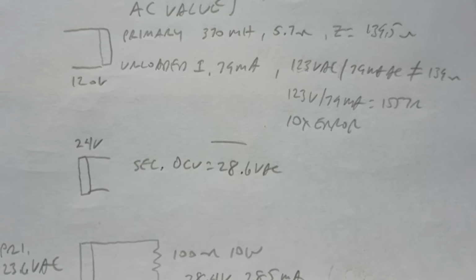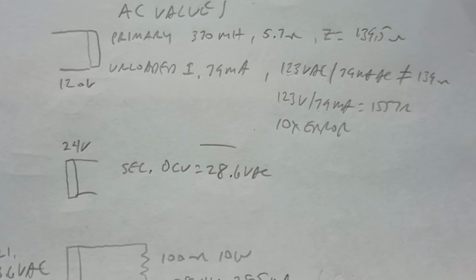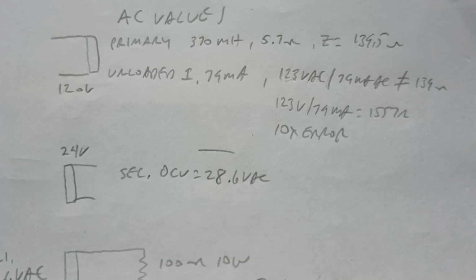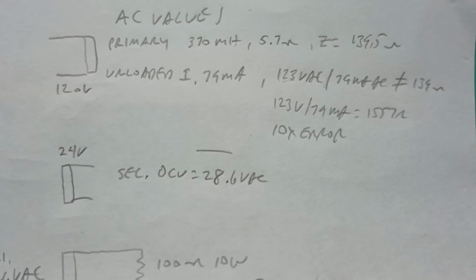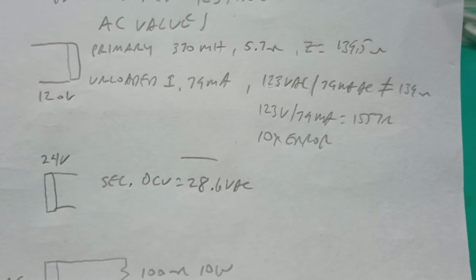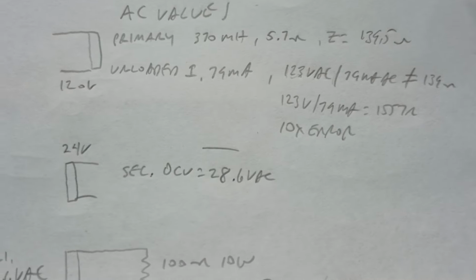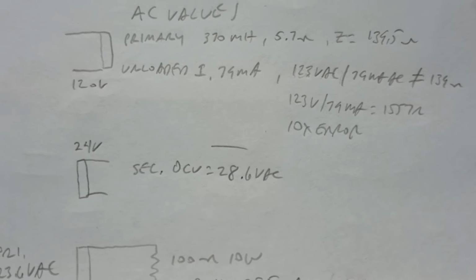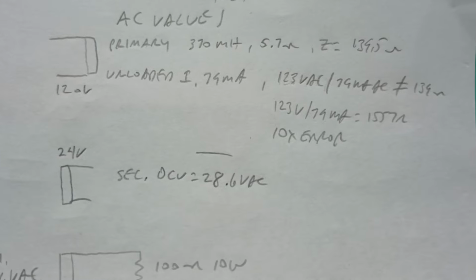Here's a diagram of the primary. I've measured with an inductance and resistance meter. The primary is 370 millihenry at 5.7 ohms. That's a total impedance of 139.5 ohms. The unloaded primary current is 79 milliamp at 123 volts AC.